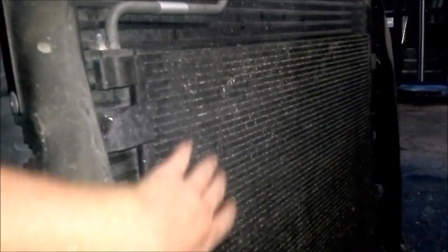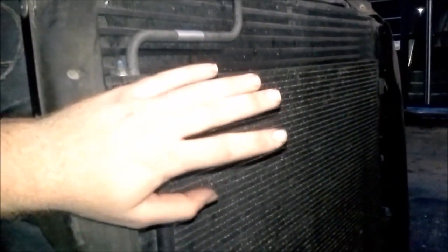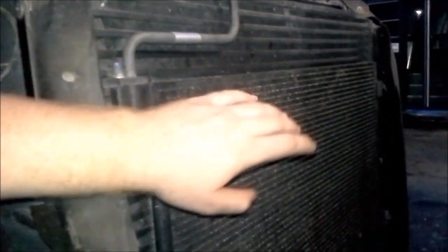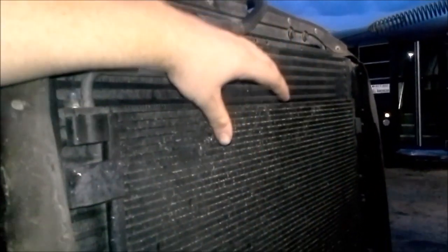What this is doing is it's taking the air and it's running it across these little fins inside the condenser. Now, you have gas flowing through these fins. The gas is hot, and if I put a pressure gauge up on the high side, you know it's significantly higher compared to the low side. So the air runs across, and the gas turns from a gas to a liquid and goes back to the low side.